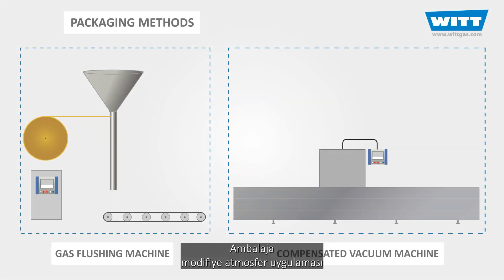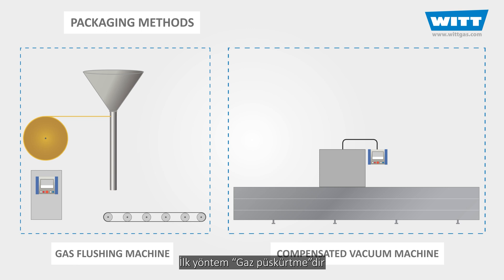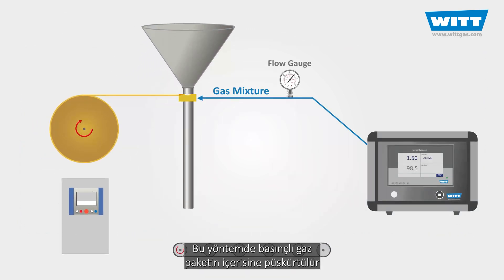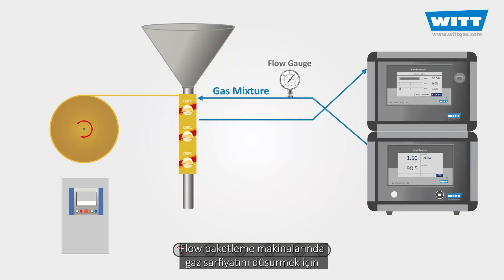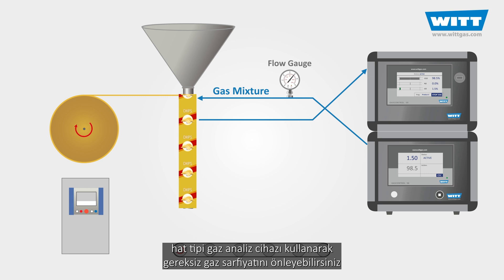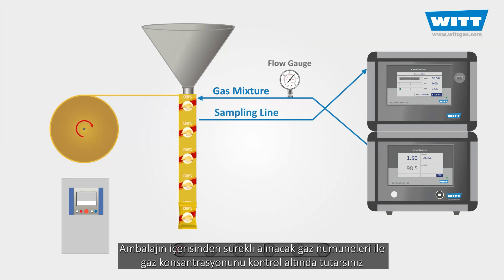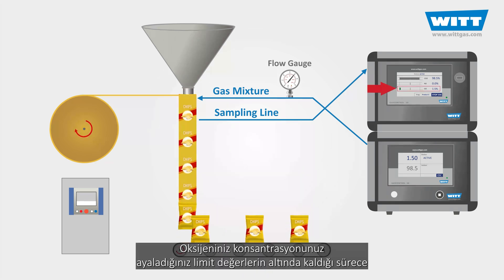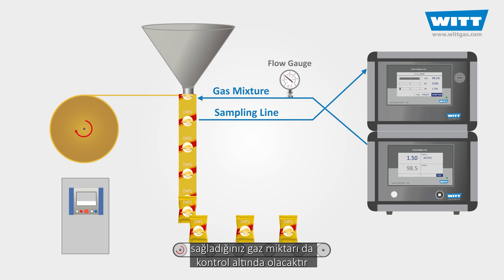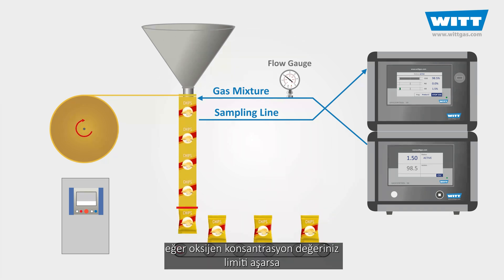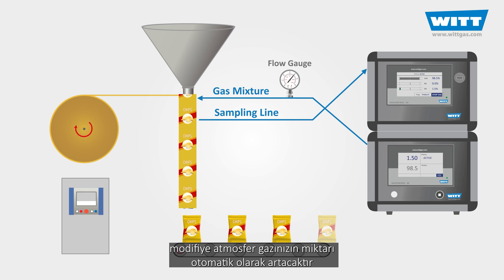How the modified atmosphere is applied to the packaging depends on the type of machine used. The first method is called gas flushing, where a pressurized gas stream is inserted into the food package so that the desired gas mixture replaces the air inside. Using an in-line analyzer, it's possible to reduce the amount of gas and save money in flow pack machines. A sample is taken continuously from the pillow bag via a lance and analyzed. As long as the oxygen value is below the set limit, the amount of protective gas is reduced; if it approaches the limit, the protective gas quantity is automatically increased.